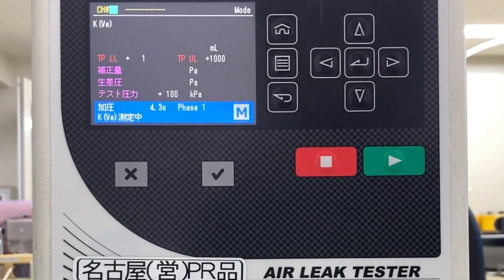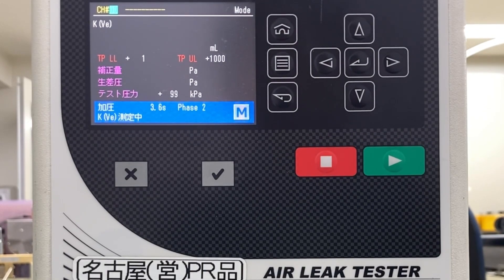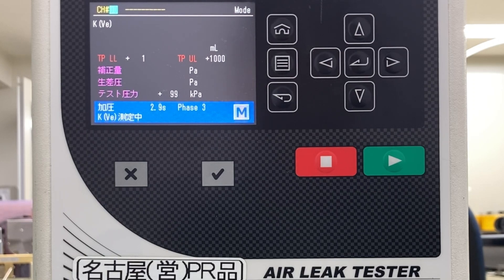Press the Start key to start 3 automatic measurements. The first measurement is a warm-up. In the second measurement, only the work is measured and the differential pressure generated by the work is measured. In the third measurement, the cal valve for the leak master connected to the calibration port opens, and a leak of 20 mL per minute from the leak master is generated during measurement.